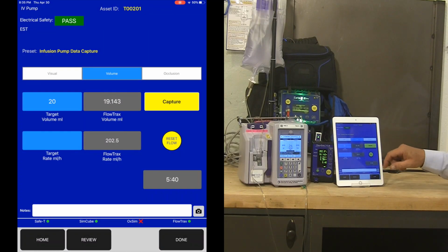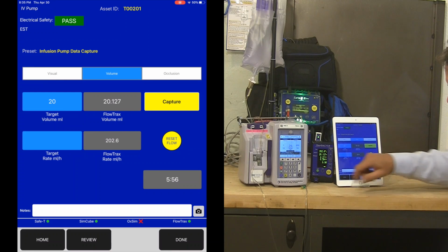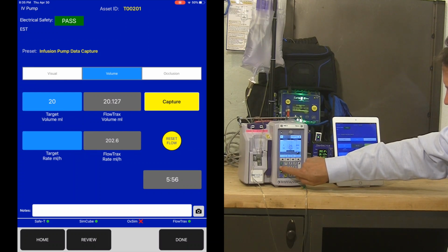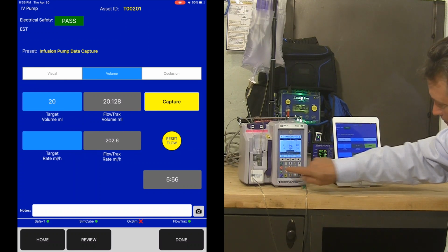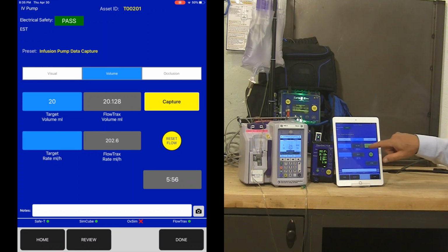Okay, so we're getting close to the end of the 20 milliliters of volume to be infused. We can see our FlowTrax volumes at about 19.5. When the pump is finished delivering its 20 milliliters, we'll be able to capture those results into our electronic record. So the pump is done. I'm going to hit stop, and I've got 20.128 for volume and 202.6 for the flow rate average over time.